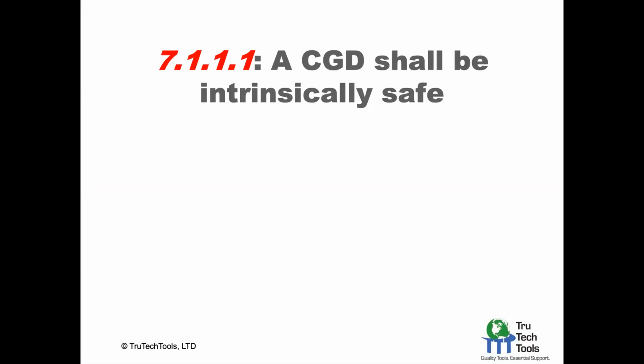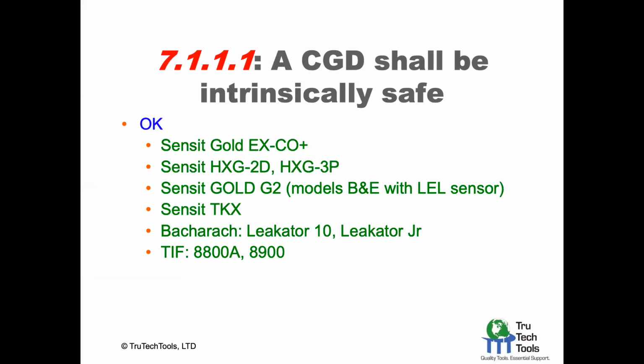So this section, 7.1.1.1, gotta love standards language: a combustible gas detector shall be intrinsically safe. So this Sensit may be a new brand to you, because they've been in the industry for utilities and fire departments. Of course, they're all intrinsically safe. The Bacharach Leakator 10 and the Leakator Junior are intrinsically safe. The TIF instruments are intrinsically safe. However, the Testo 316-1 is not intrinsically safe. So that means Testo gets booted from the island at step one, at 7.1.1.1.